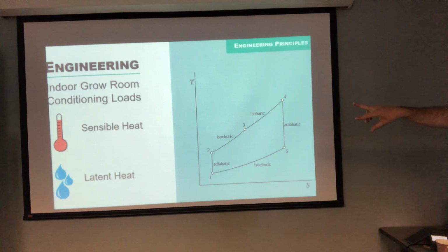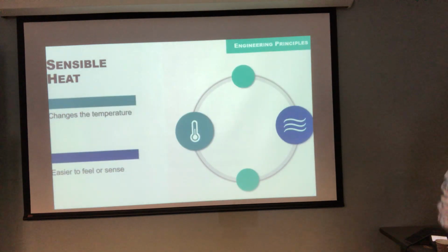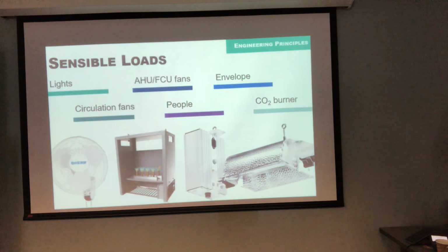There are two types of heat we care about: sensible heat and latent heat. Sensible heat is a change in the temperature of the air—it's the change you can sense, hence the word sensible. The sources of sensible loads in your facility are the lights, the fans in your air handling unit or fan coil units, loads coming in from the envelope, circulation fans, to some extent people, and if you're using a CO2 burner, which I don't think anybody is, that can be a source. If you're using portable dehumidifiers, they introduce a lot of sensible load back into the space, and we'll touch on that in a minute.